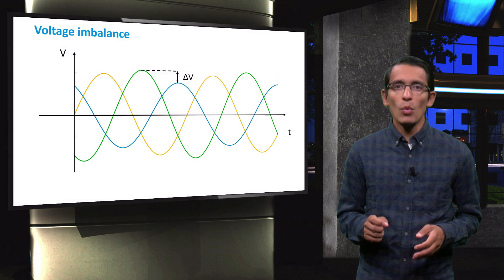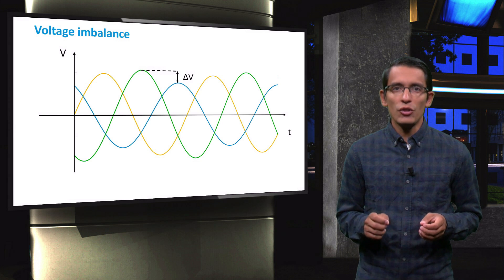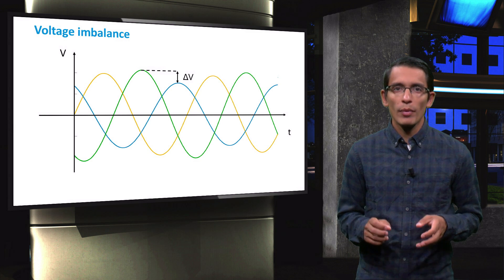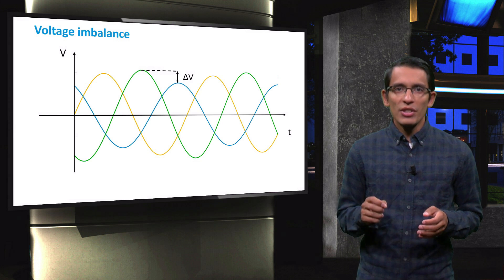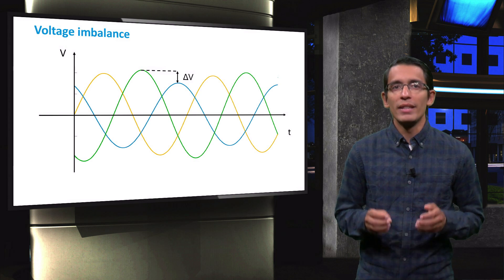This is the reason why at high PV penetrations, the cumulative size of all systems connected to each phase should be as equal as possible. Generally, all systems with installed power above 5 kW peak should be connected to an inverter which can guarantee a balanced three-phase output.